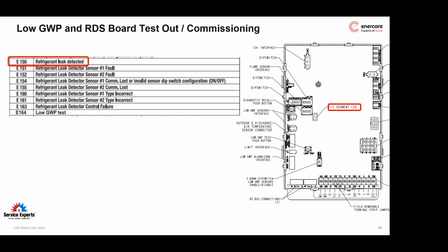You were saying that it would not shut off the cooling if it was a sensor fault. It would just show a fault, if the sensor was faulty, correct? Yeah. So if you look over here, sensor fault, refrigerant leak detection sensor fault, or sensor type is incorrect. If there was a sensor fault, it'll give you a different error code, but it won't lock out your heat. They're two different faults. That's a refrigerant leak detected fault, and that's a sensor fault.